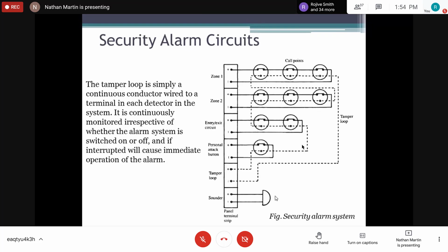All right, security alarm circuit. This is just the same thing as a fire alarm, a similar type of arrangement. You have an open circuit and you have a closed circuit, and they are showing you the different zones of control and how they are tied into your main panel. So this is your main terminals, and this is your sensing devices or your call points, right? And then we have a tamper-proof loop, right?